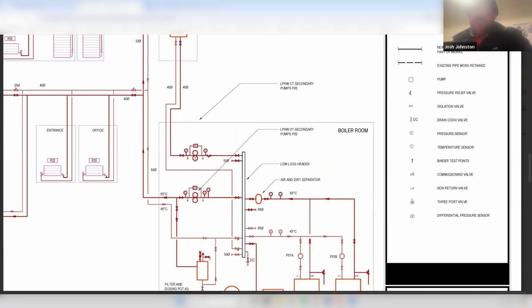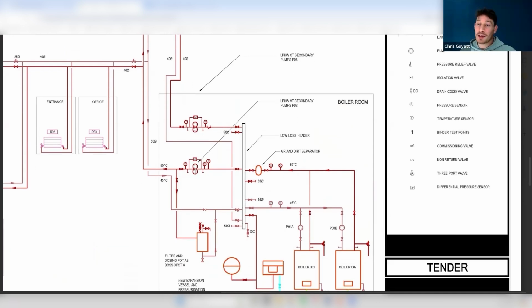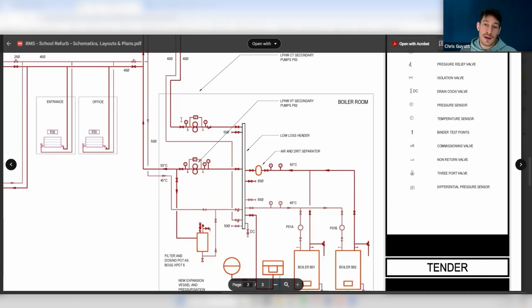This is pretty common in commercial and industrial premises, where it's critical that if something goes wrong with one of these pumps, we can just switch over to the other pump and still have heating and hot water. As soon as it goes into fault, we or the client can be made aware, and we can fix that pump whilst the other one is running. We're never without heating or hot water, as we talked about yesterday - you've seen that before and worked on pumps like that.